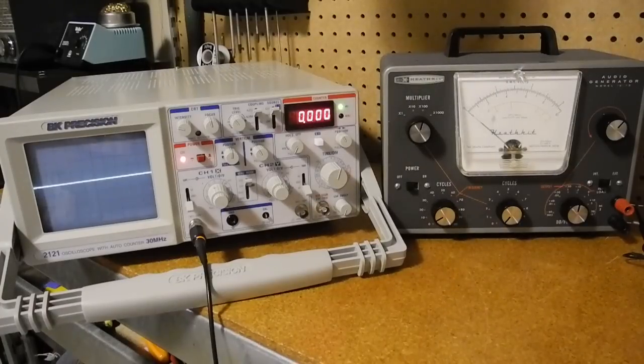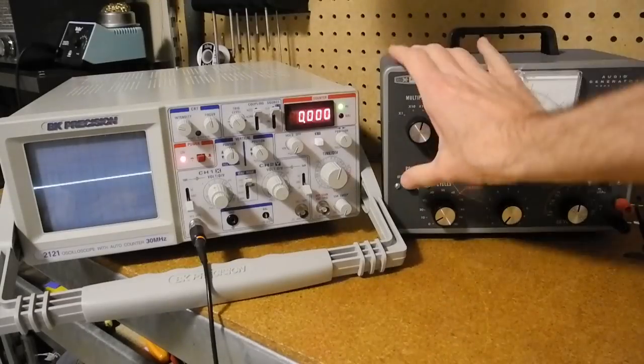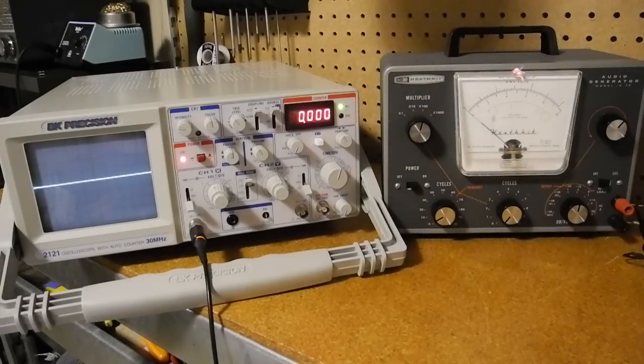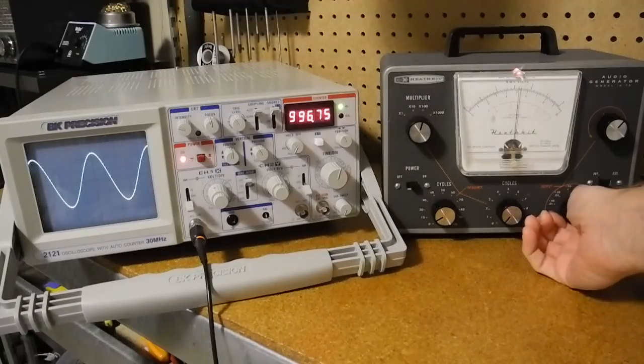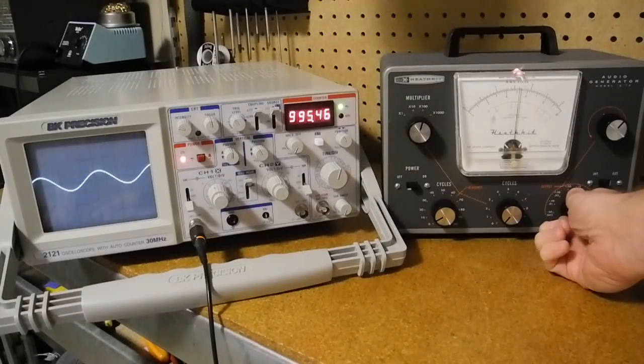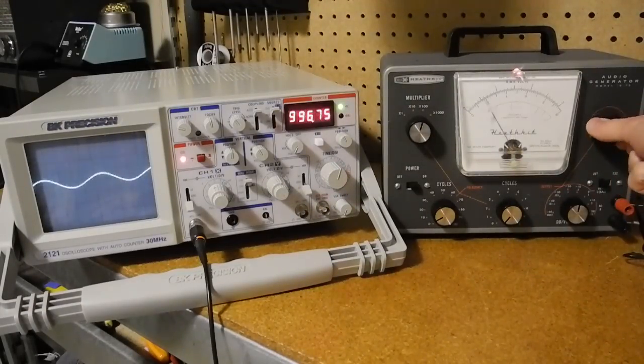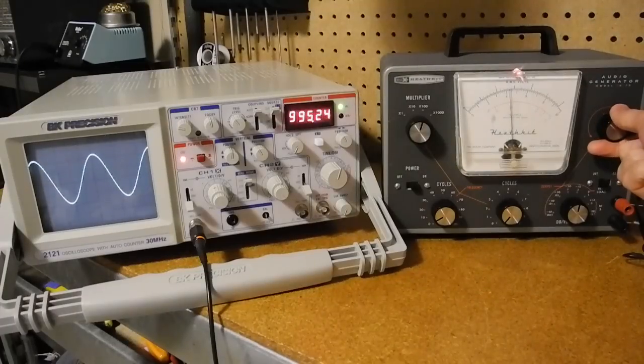Let's take a look at the unit in operation. I've connected the output to an oscilloscope. When powered on cold, it takes a few seconds for the tubes to warm up. The output level is set by the attenuator using the 8 ranges and fine control. The meter shows the output level as is changed by the fine control. It doesn't change with each range as it scales depending on the range.